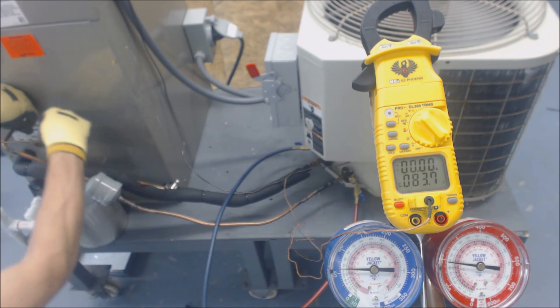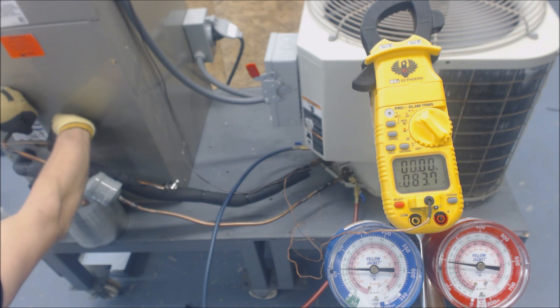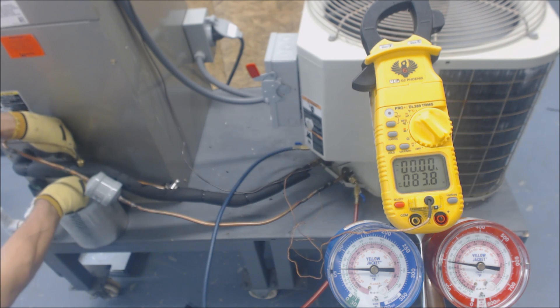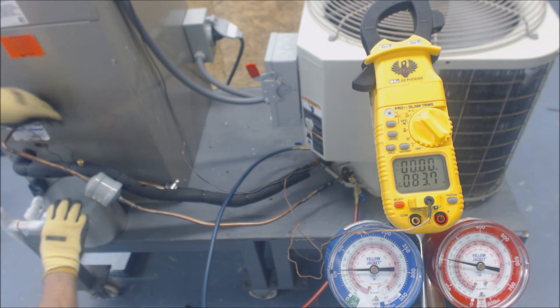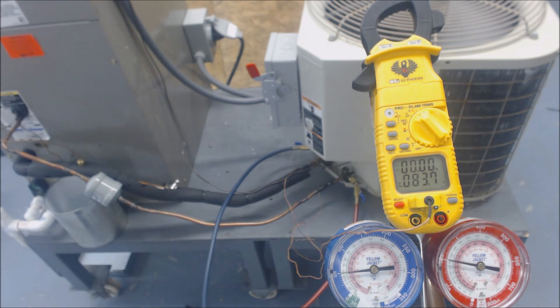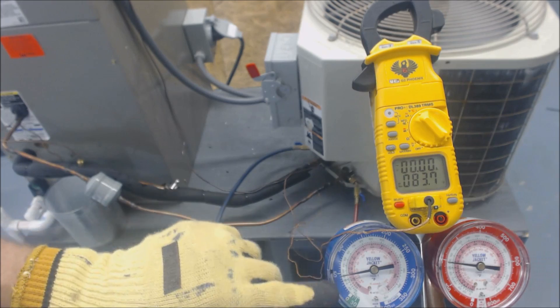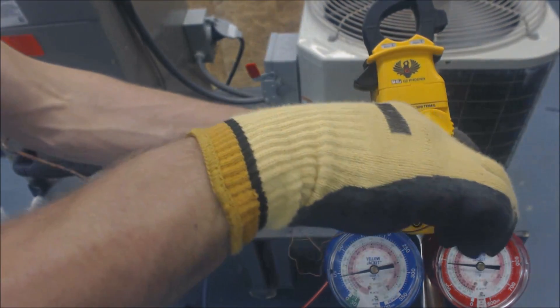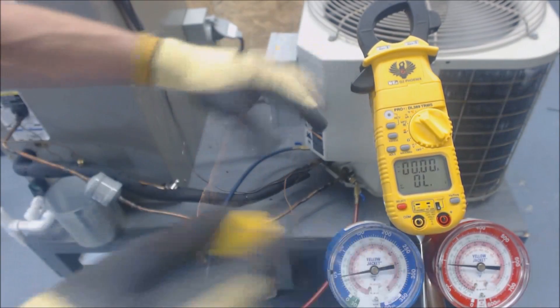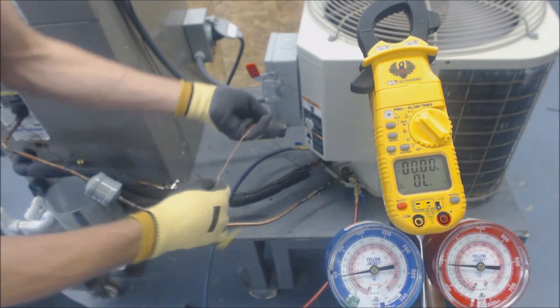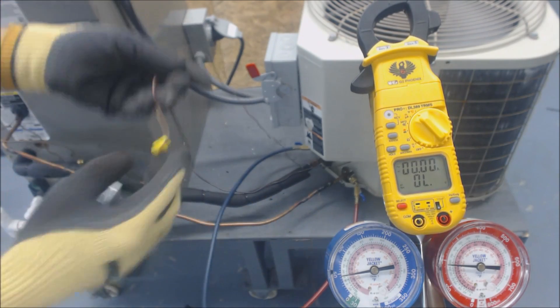The ice water is right around 33 degrees. You want to make sure that you do not pinch the line coming off the TXV, as it has refrigerant in it at all times. We're going to put that in ice water and I want you to watch what happens. The suction side, see how it's dropping.